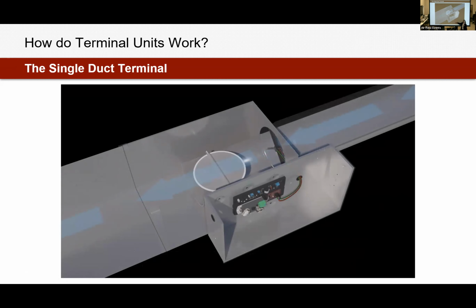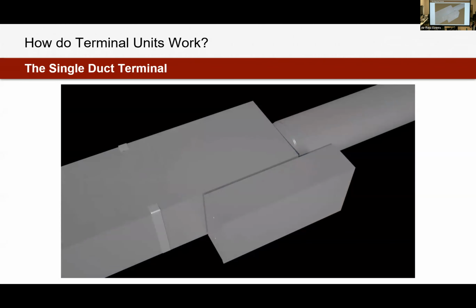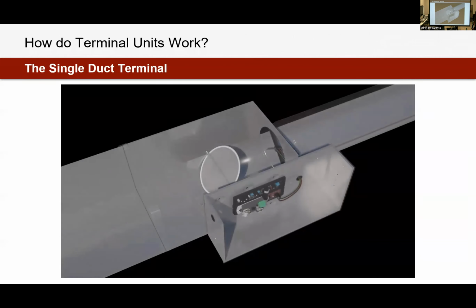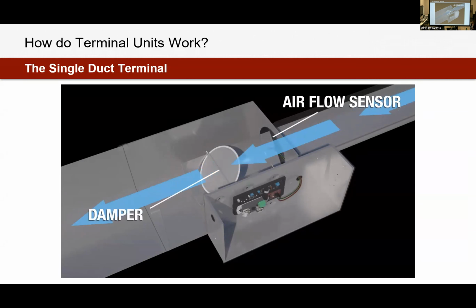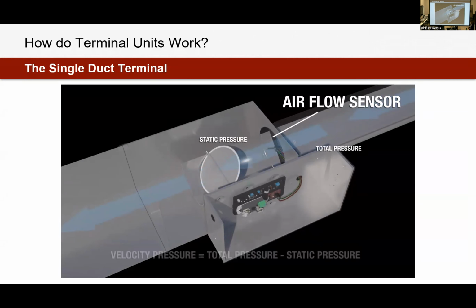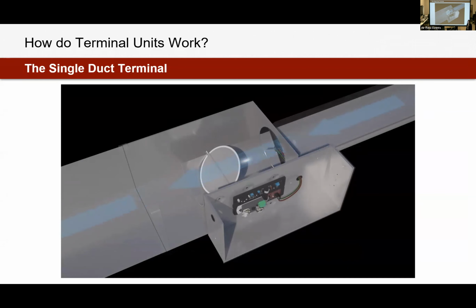So your controller is kind of the brains of the single duct box. We're going to be measuring airflow, sending a signal to the controller, and then adjusting the damper. Again, the most simple type of terminal unit, really all we're doing is changing the volume of air given to a space. This is your single duct box. Later on, we're going to look at fan powered boxes, which is a combination of this with a fan.